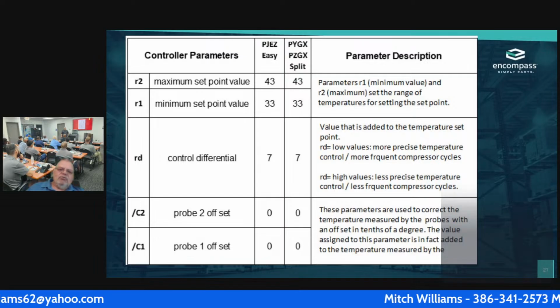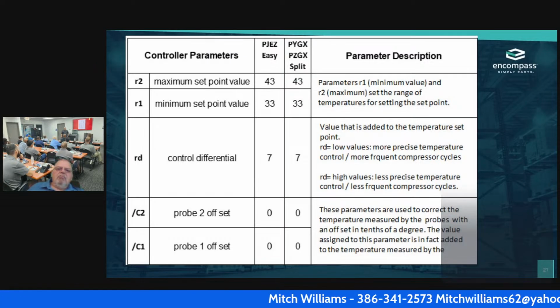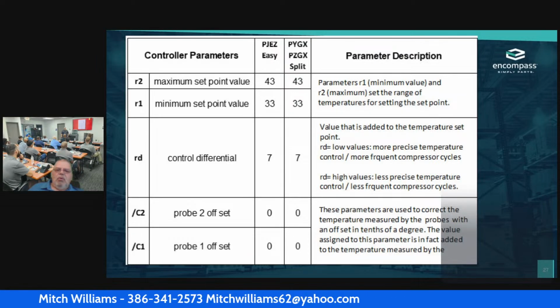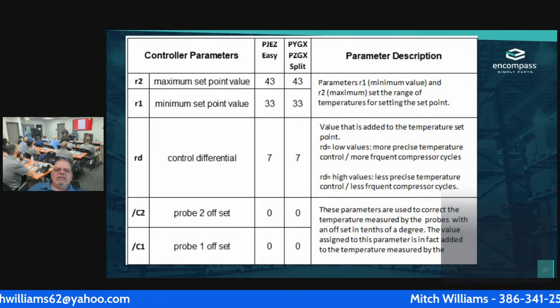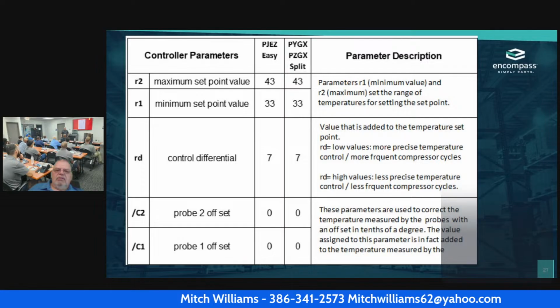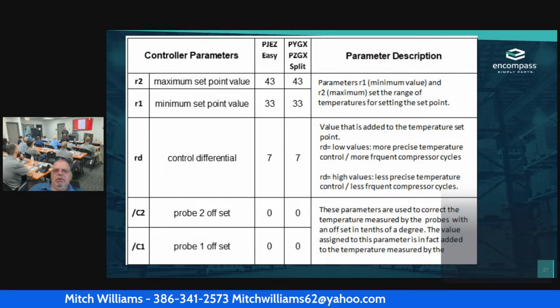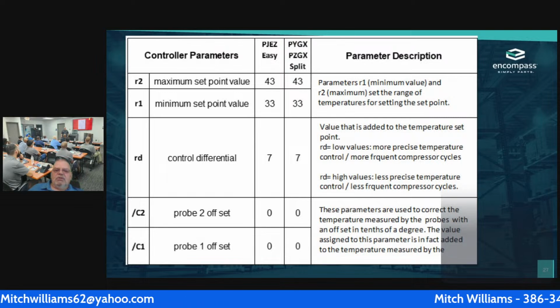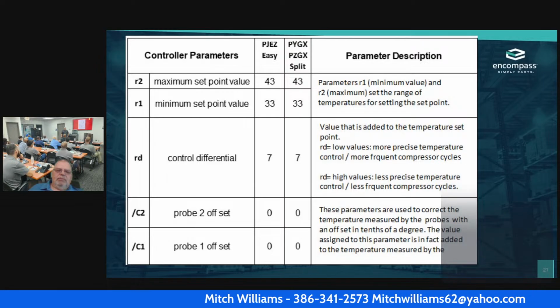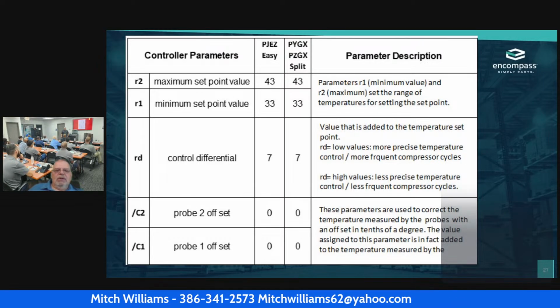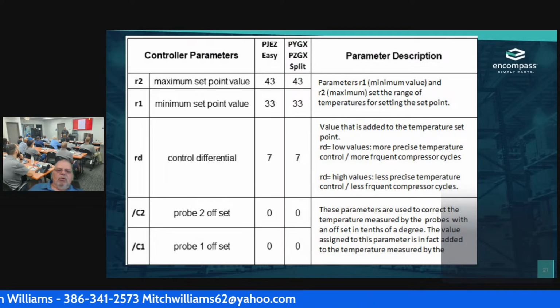Okay. Control parameters. Once again, both of them are set at 43. Maximum set point value, and then the minimum set point value. The maximum set point is 43. The minimum set point is 33 on both of those controllers. The parameters are the minimum value, and R2 is the maximum value, and I can set the range of temperatures at that set point.